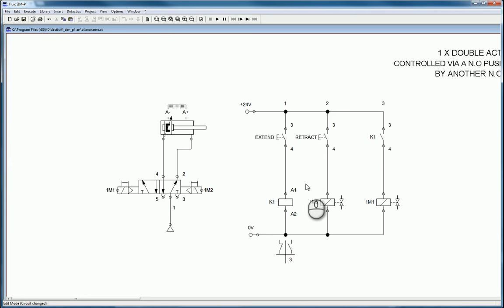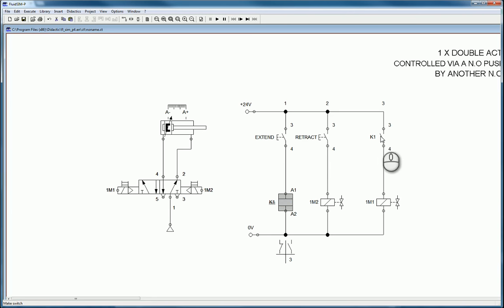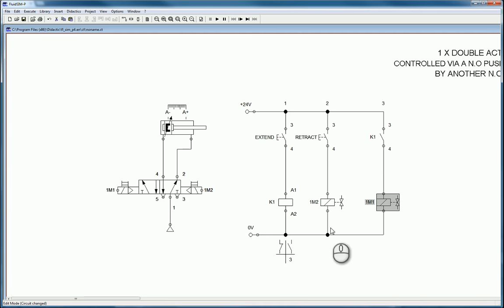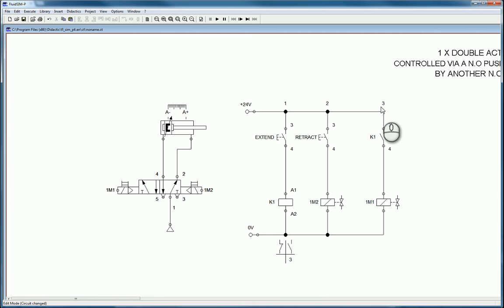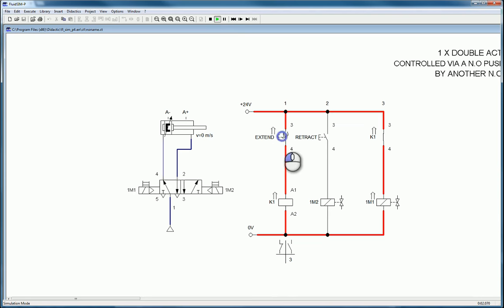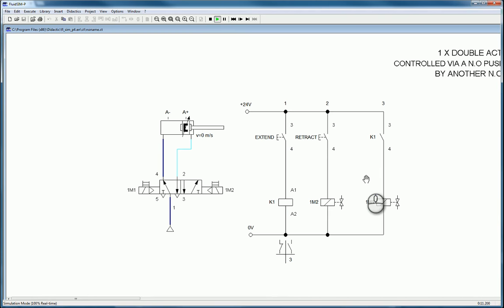Now in rung one, instead of the push button going directly into the valve solenoid, it goes into the relay and the relay closes its contacts, which then indirectly controls the valve solenoid. The contacts at the bottom show which rungs have which connections — the normally open contact for K1 is on network three. Press play: pressing the button activates the relay, K1 closes the contact, which operates 1m1. Letting go turns it off but the cylinder stays extended due to the valve type.